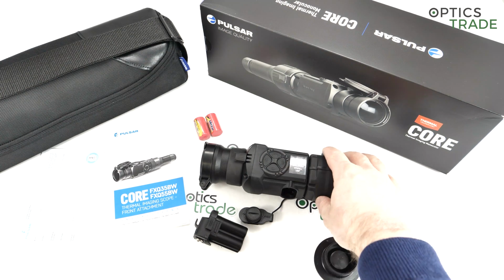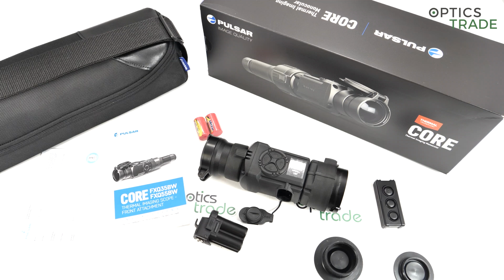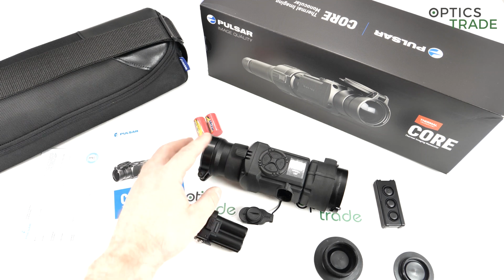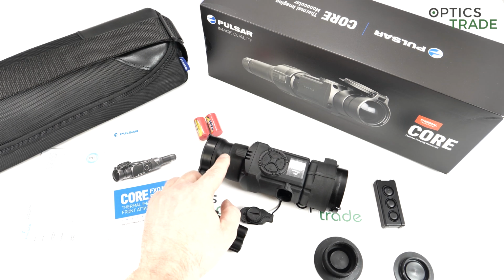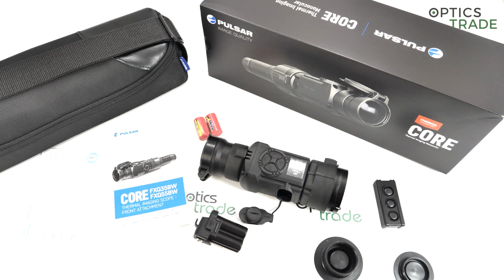The calibration modes on this device are 3, so that means manual, semi-automatic and automatic. For those of you who are not really familiar with thermal imaging devices, the calibration is a procedure which happens every 30 seconds or something like that, when the sensor inside gets reset, because otherwise some pixels would get saturated and you would lose contrast and image quality.